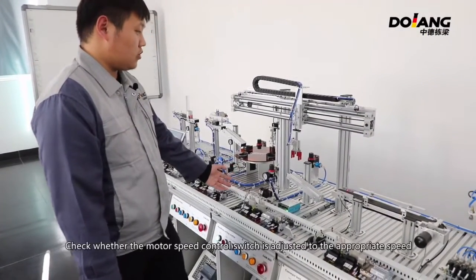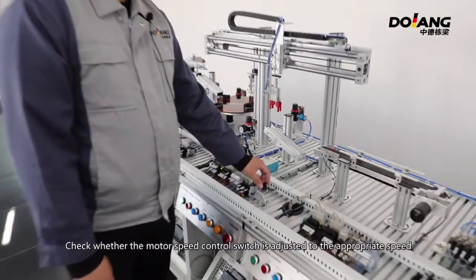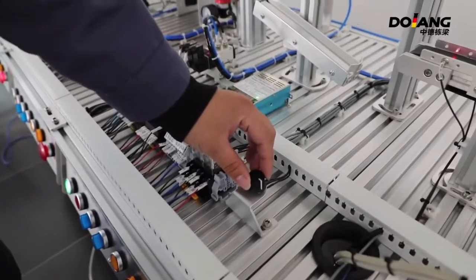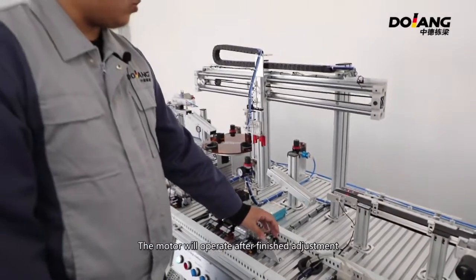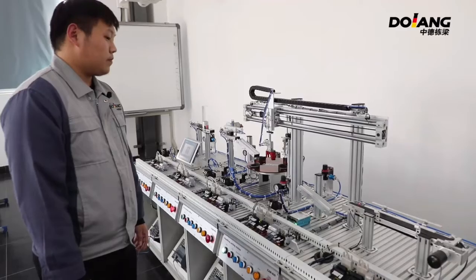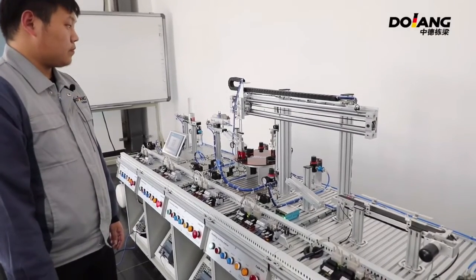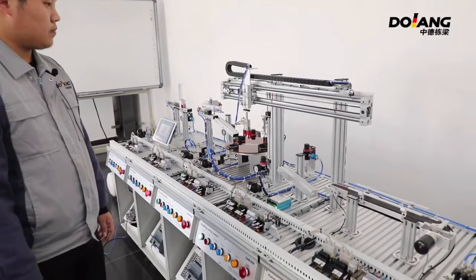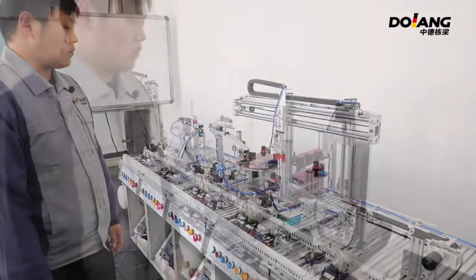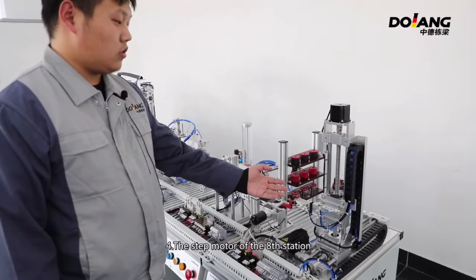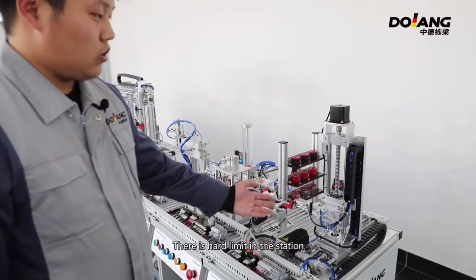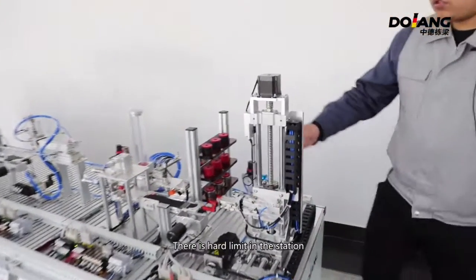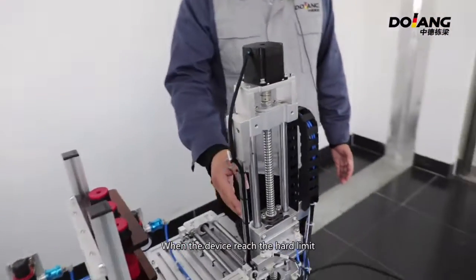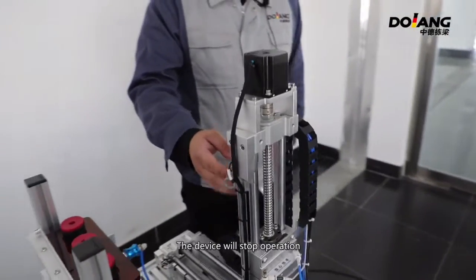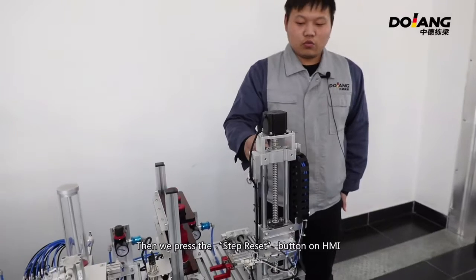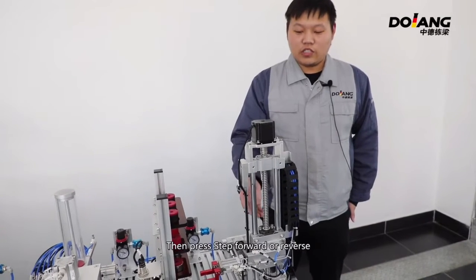Third, when the fourth station doesn't operate, check whether the motor speed control switch is adjusted to an appropriate speed. The motor will operate after finishing adjustment. Four, the stepper motor of the 8th station. There is a hard limit in this station. When the device reaches the hard limit, the device will stop operations. Then we press the step reset button on the HMI, then press step forward or reverse.